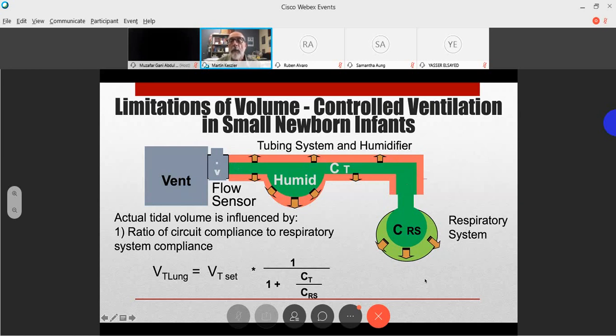not a big problem. But when you attach a 600, 800 gram preterm infant to this circuit, and those babies' lungs are a fraction of the volume of the circuit and humidifier, the proportion of tidal volume lost to compression is greater. And then, of course, we have the problem with the uncuffed endotracheal tube, with the variable leakage around the endotracheal tube. You can, up to a point, compensate for the circuit compliance, and some devices have that provision to use an automated compliance compensation, but that completely breaks down when you have a leak around an uncuffed endotracheal tube.